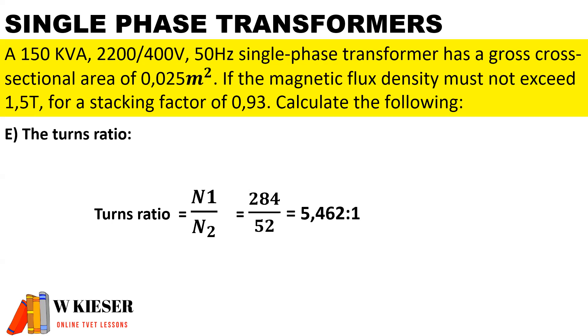To determine the turns ratio, we have the number of turns on the primary side versus the number of turns on the secondary side. You'll notice that the 52 is a smaller value, it will go into itself once and it will go into 284, 5.462 times. Therefore, we have a ratio of 5.462 on the primary and one on the secondary.